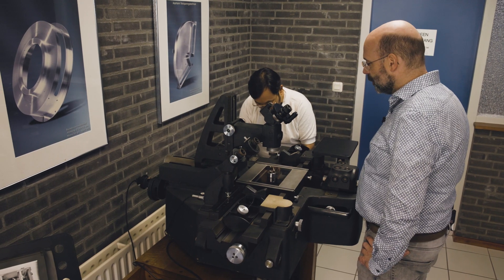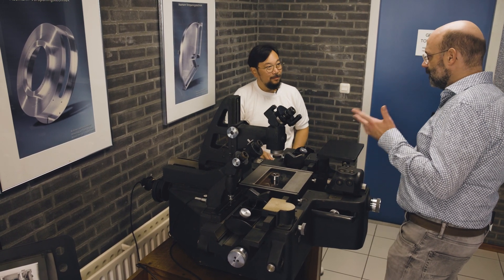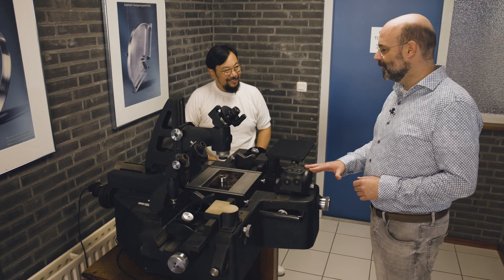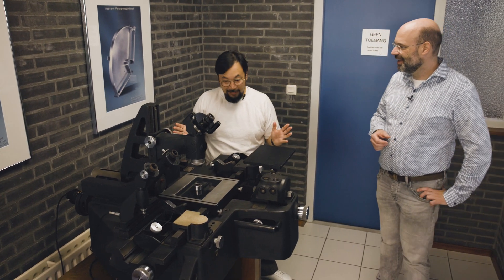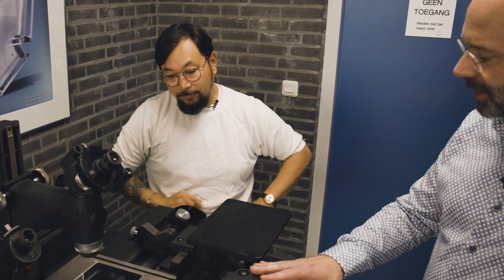So my reading is that the ring gauge is three microns over. Wow. Now there's a discussion — it's not calibrated, so is it the machine or is it the ring gauge? Or maybe it's the operator. But it's a 20 millimeter ring gauge and we've definitely read something that is absolutely feasible. And this is just a simple two-point distance measurement.